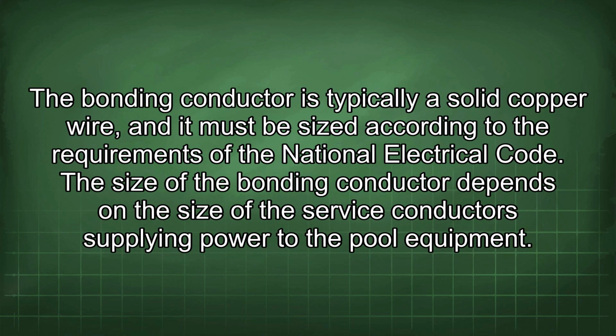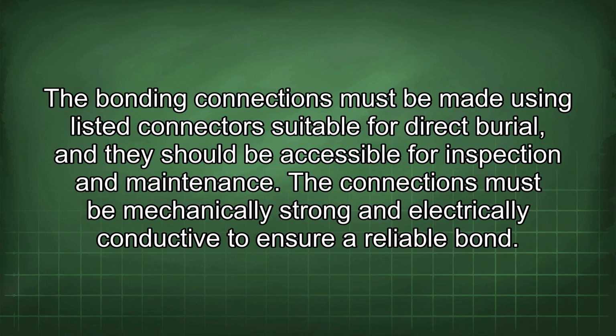The bonding conductor is typically a solid copper wire, and it must be sized according to the requirements of the National Electrical Code. The size of the bonding conductor depends on the size of the service conductors supplying power to the pool equipment. The bonding connections must be made using listed connectors suitable for direct burial, and they should be accessible for inspection and maintenance. The connections must be mechanically strong and electrically conductive to ensure a reliable bond.